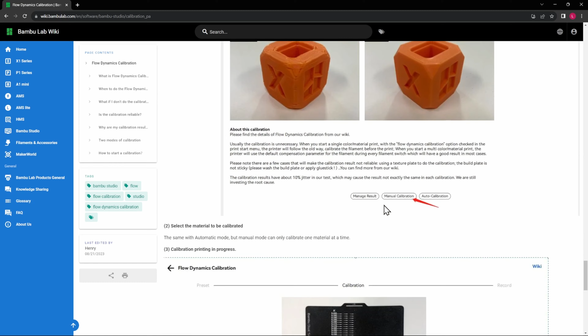And there's two different methods here, the line method and a pattern method. So within the wiki here, we can see it go through the flow dynamics calibration as well as the line method, right? In this method, you pick the best line that it's supposed to be, and that'll be your factor K value or whatever. But it also has a pattern, and it doesn't say anything about the pattern here. And I've never done the pattern before, so let's select the pattern and let's see what that does. So we'll go ahead and hit calibrate on there. And we'll see that it has this cool little chevron looking thing here.